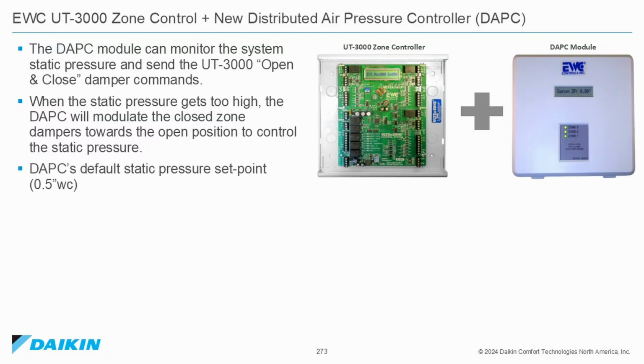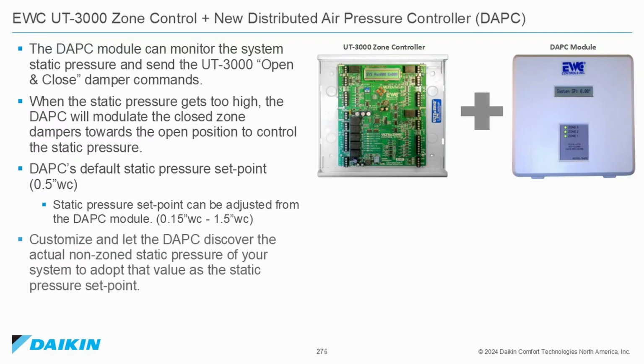The DAPC's default static pressure set point is 0.5 inches of water column. The static pressure set point can be adjusted from the DAPC module between 0.15 inches of water column and 1.5 inches of water column. Customize, and let the DAPC discover the actual non-zoned static pressure of your system and adopt that value as the static pressure set point.